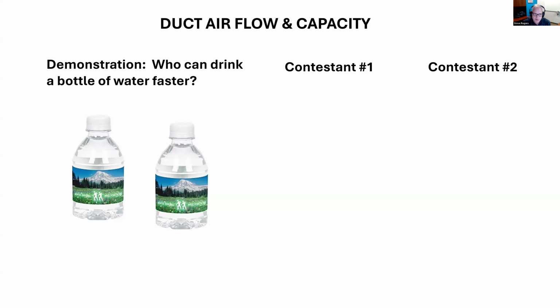So when you're thinking about a retrofit system, it's really important to evaluate the capacity of the existing ducts. And especially when you're retrofitting a furnace with a heat pump, because if you look at how many BTUs can be delivered with the airflow in the duct system, furnaces deliver hotter air, and therefore it takes fewer CFM of airflow to deliver the heat. So for the same heat to be delivered to a house, a heat pump needs more airflow. And so it's important to understand what the limits of the existing duct system are.